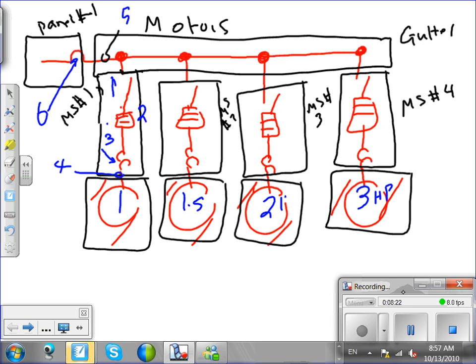The system voltage is 240 volt, single phase. The system is a 240 volt single phase system. Anybody has an issue with that? If it was a 3-phase system, we're going to go to just a different table, same calculation, which we will be doing in the commercial more often. Any question guys about the system? Everybody knows how the system is set together.